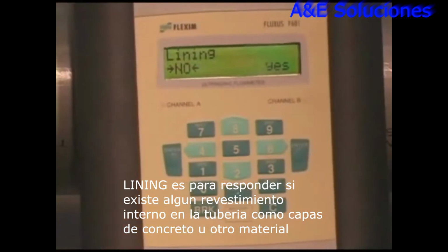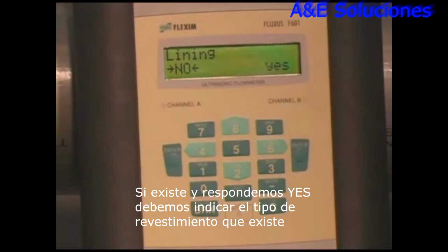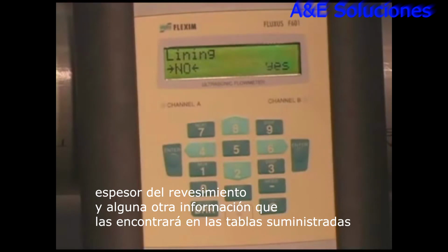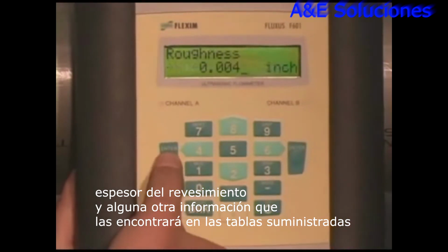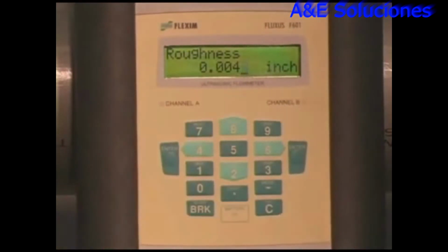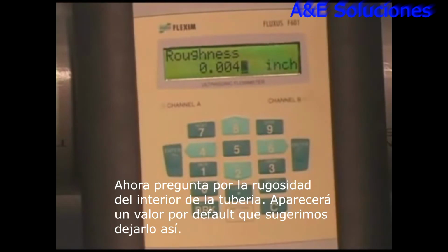Lining, it's asking about an internal liner. Some pipes have internal liners. Common would be ductile iron pipes that have internal cement liners. If you choose yes, it'll ask you what the material type is of the liner, and then it'll ask you to enter in the thickness of the liner. Again, if you look at the pipe chart, you'll find on the ductile iron also typical liner thicknesses. Okay, we'll say no on the liner. The next thing is pipe roughness. Now, the meter installs a default value for pipe roughness. That's internal roughness, and you're best to not think too much about that and just leave the meter's value alone.